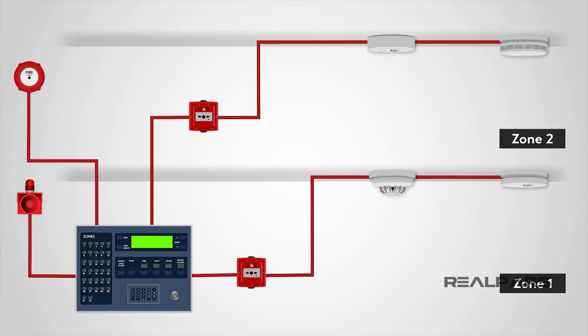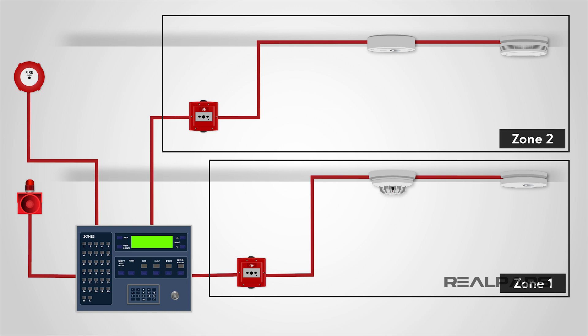In a conventional fire alarm system, physical cabling is used to interconnect several call points and detectors, the signals from which are wired back to the main control unit. Call points and detectors are arranged in zones to simplify locating the cause of the alarm.